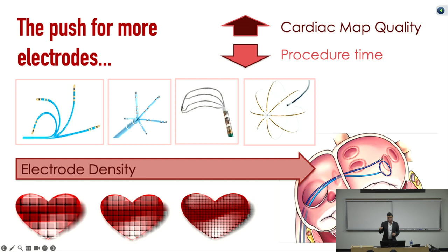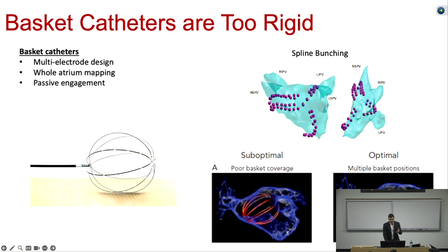So they started to make these basket catheters, which fill up the entire chamber, but they really didn't work well. The reason they didn't work well is, one, they're using nitinol, which in the medical field is considered a highly elastic alloy that should be highly conformable, but it's still about 1,000 times stiffer than a polymer that you could use. So what you end up seeing is that maybe you're only getting 40% of the sensors making contact with the cardiac tissue. The other thing is something called spline bunching, where the rigidity of these splines causes them to bunch into different crevices of the heart, and it becomes difficult to get them to go to the full surface of the heart. So these were a couple of reasons why this device ended up not being effective.